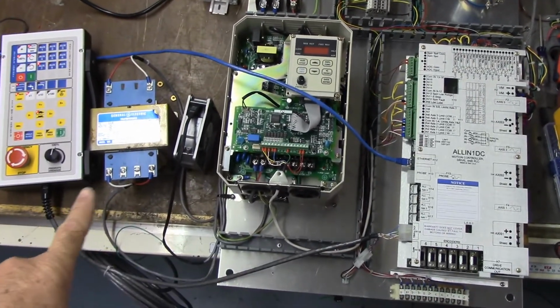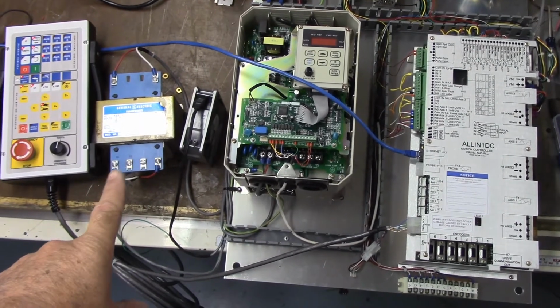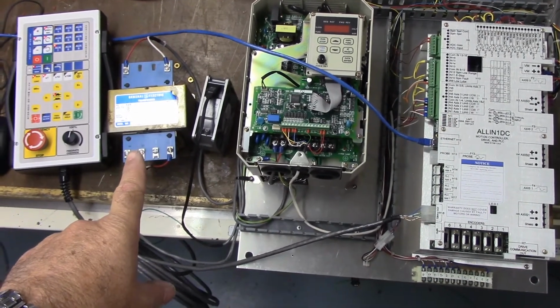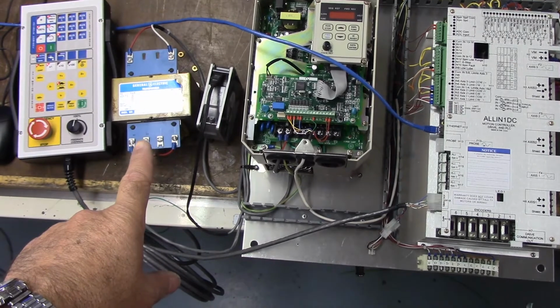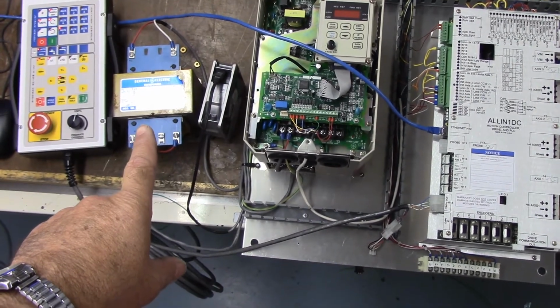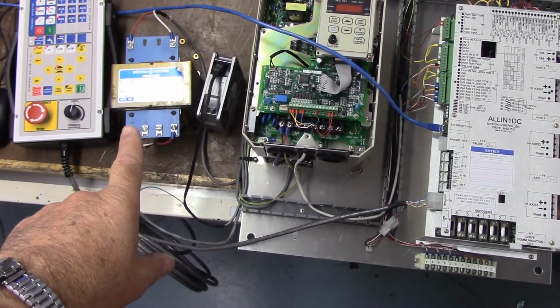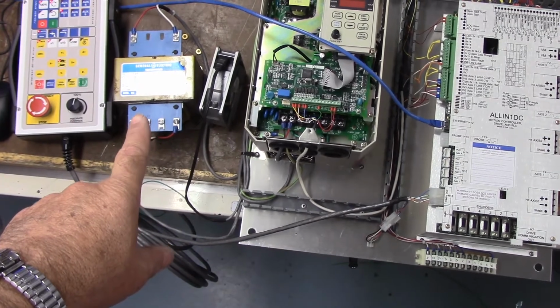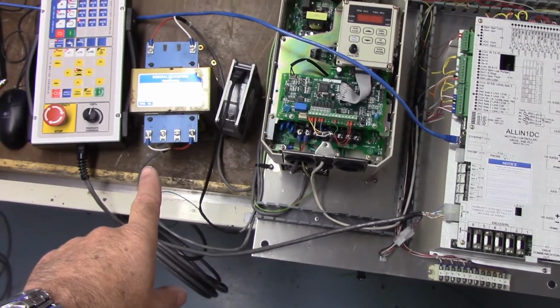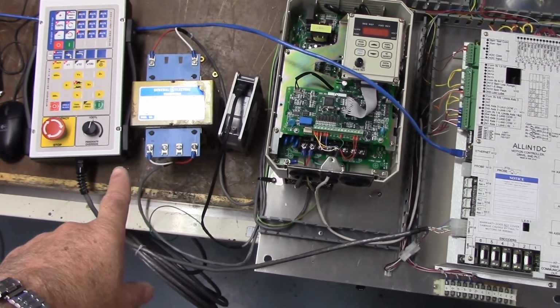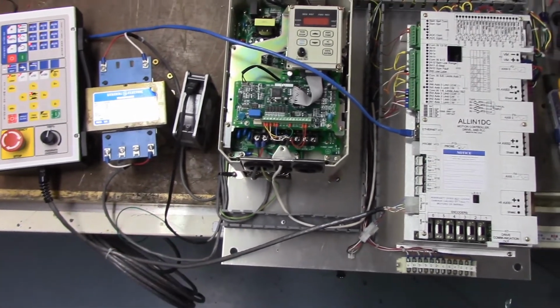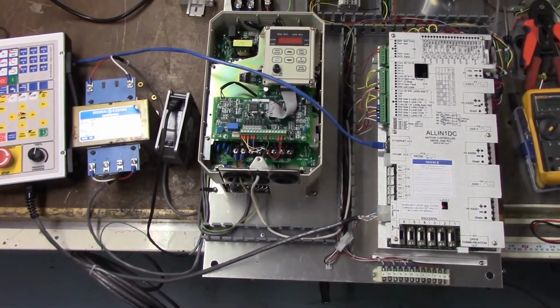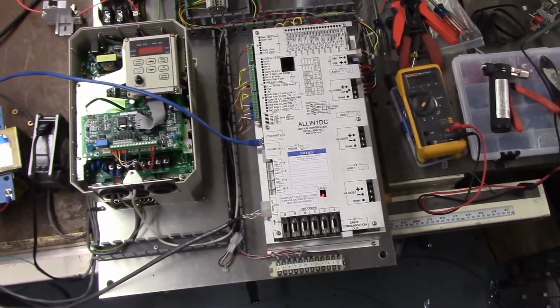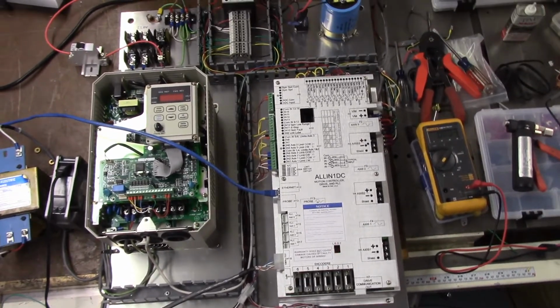And right here, this is a step down transformer for the servo motors. Their max terminal voltage is 140 volts. This is putting out about 80 volts of AC, and then once it's rectified it's times 1.414, whatever that comes up to. We can take a look at that voltage here shortly.